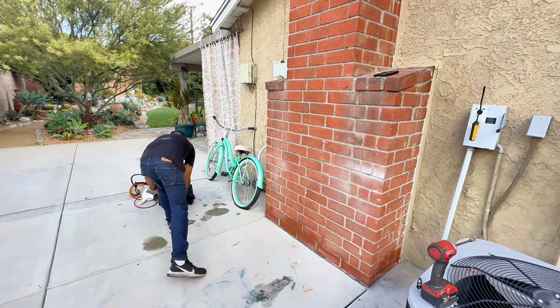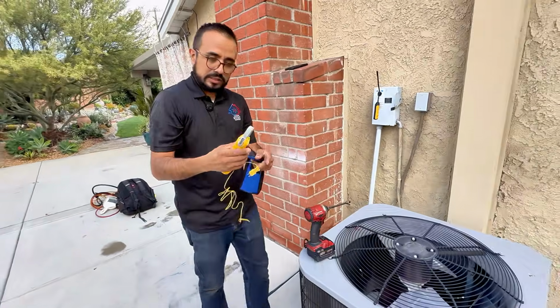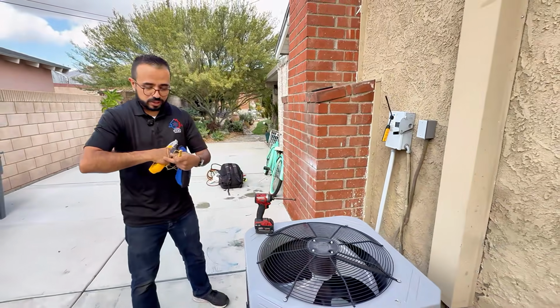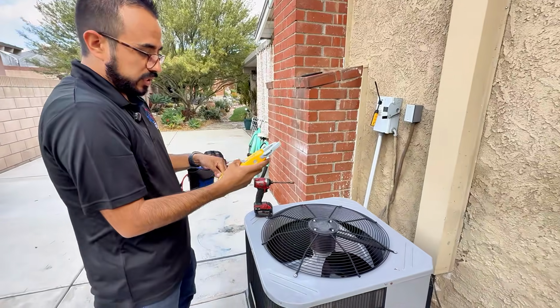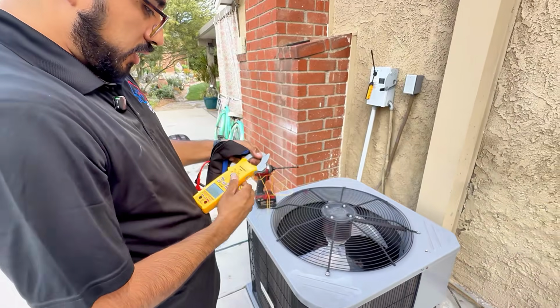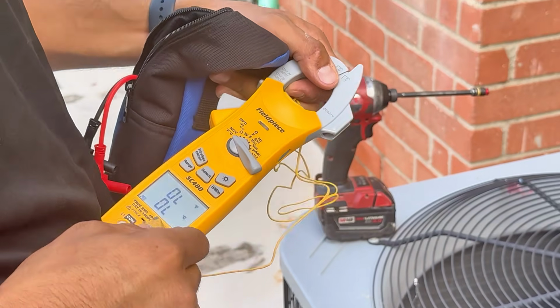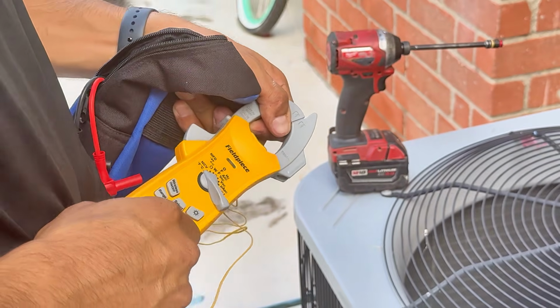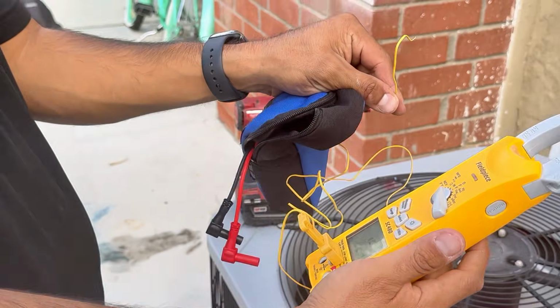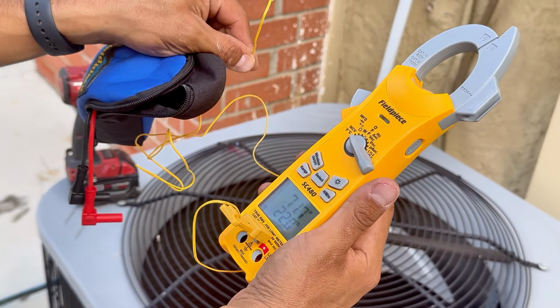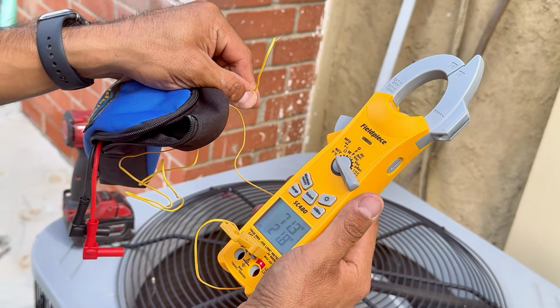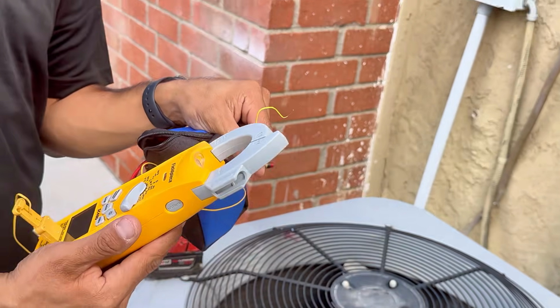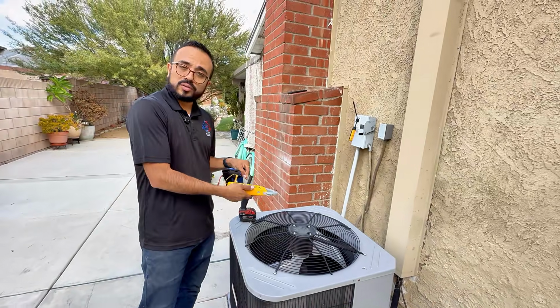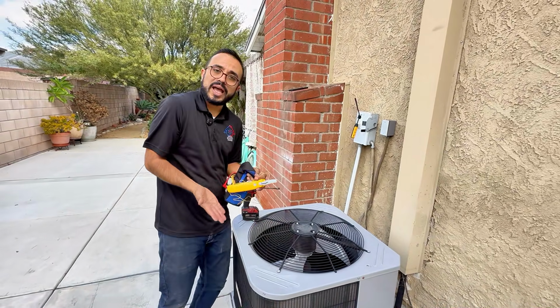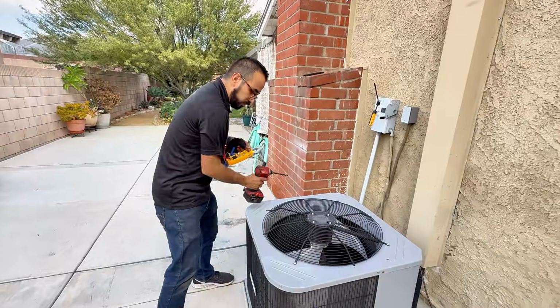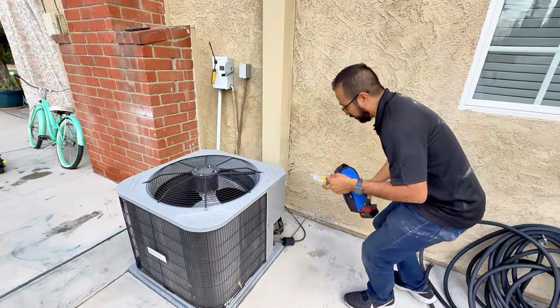I'm gonna go get my meter, and just to give you guys an example, you don't need that psychrometer. If you get a meter, it comes with a thermocouple, and you can just put it on Fahrenheit, put it on, and it tells you what your temperature is just by staying here. Stay here, and right here it's reading, what is it, 71. And it dropped in temperature because there's a little bit of wind, I feel it right now. So we might have to block this a bit to bring up the head pressure. But I was just going to show you that you don't need those expensive tools to do what you've got to do.